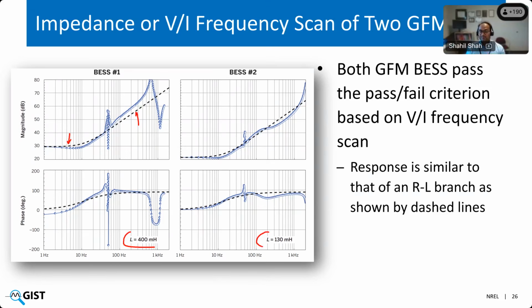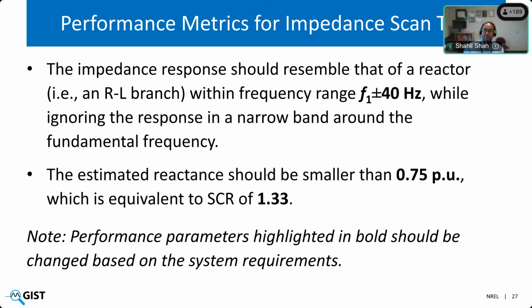This inductance you can convert into the short circuit ratio or dynamic short circuit ratio, because we are not really looking at short circuit currents, but just the impedance of this resource within this particular frequency range. So the performance metrics is that the impedance response should resemble that of a reactor, similar to a pass-fail criteria, and also that the reactance that you estimate from this V by I or impedance scan should be smaller than a particular threshold, in this case 0.75 per unit. What it means is that this particular resource should give a short circuit ratio or dynamic short circuit ratio of more than 1.33, which is just the inverse of 0.75. If the inductance or reactance is even smaller, that means that the grid forming resource is contributing a higher level of grid strength to the system.